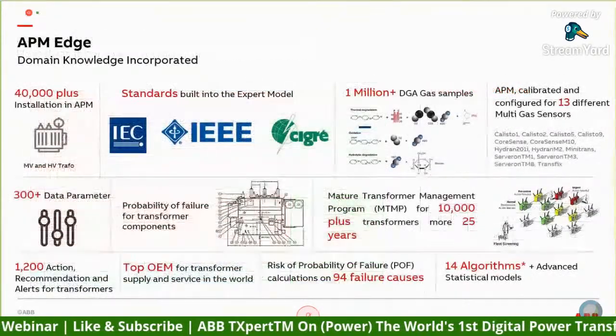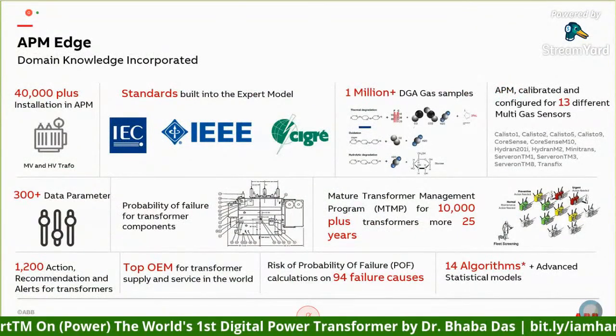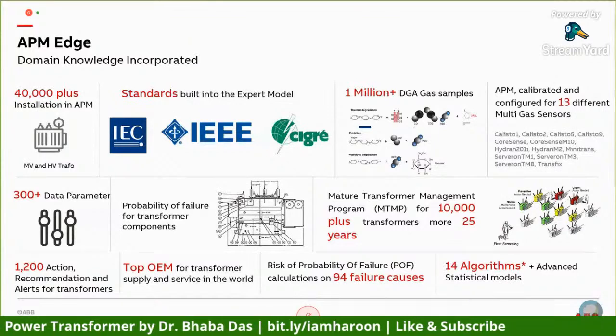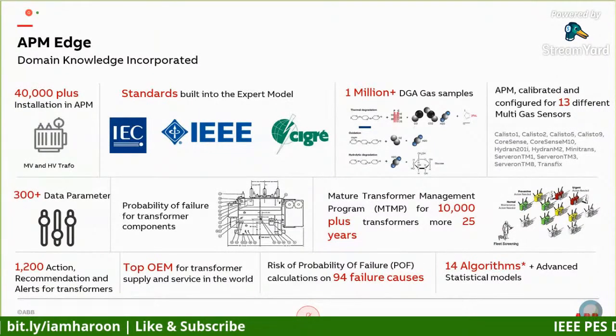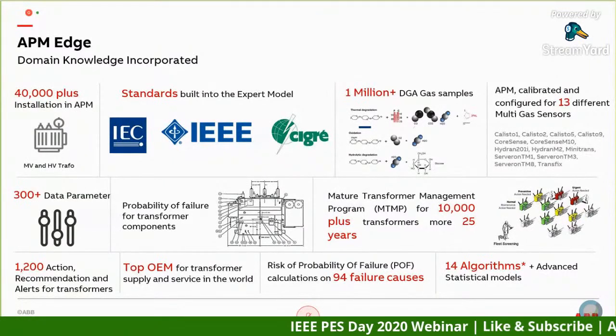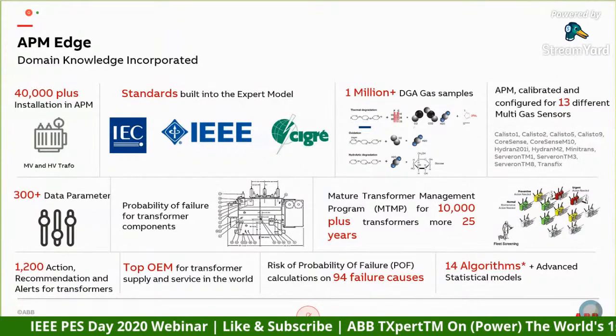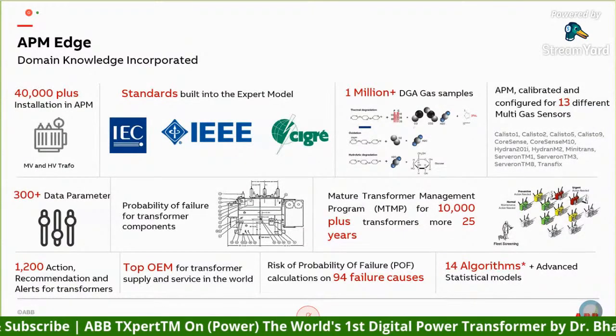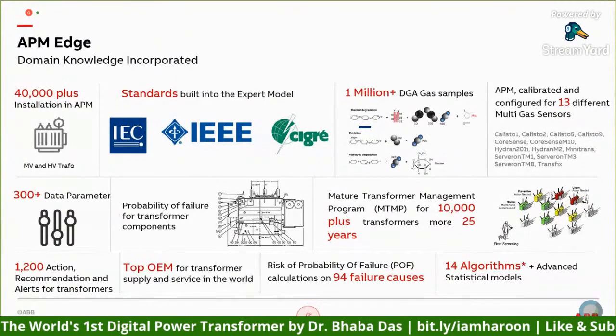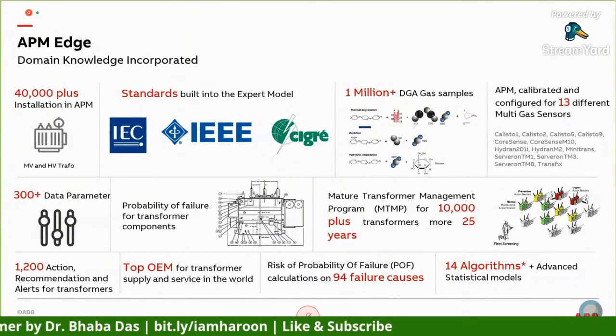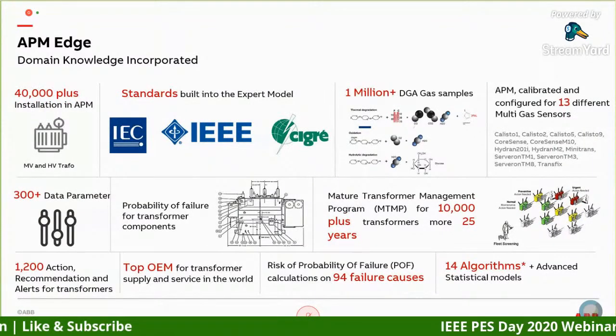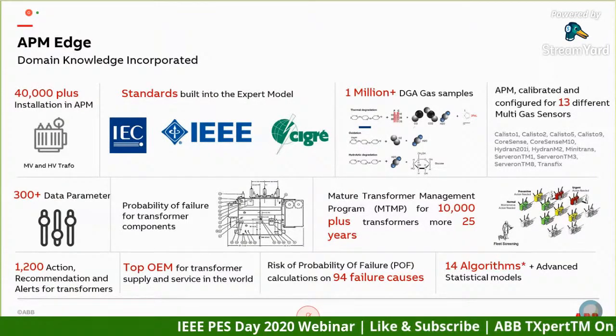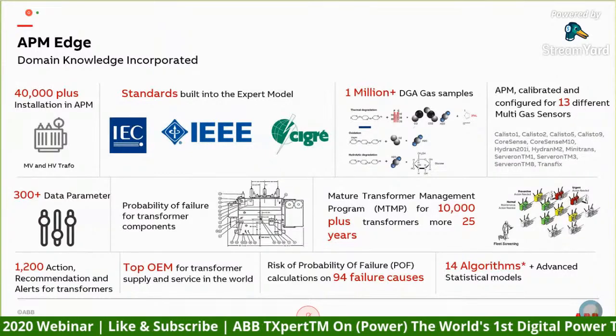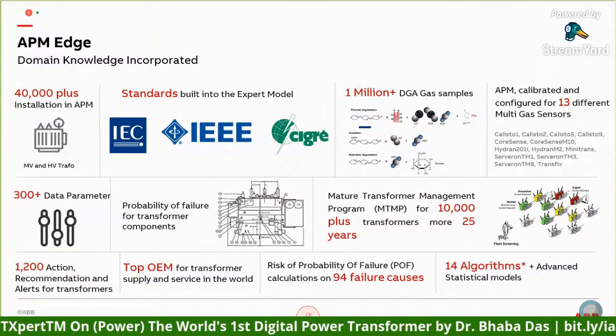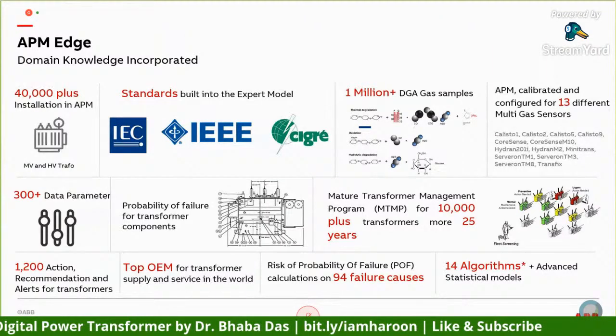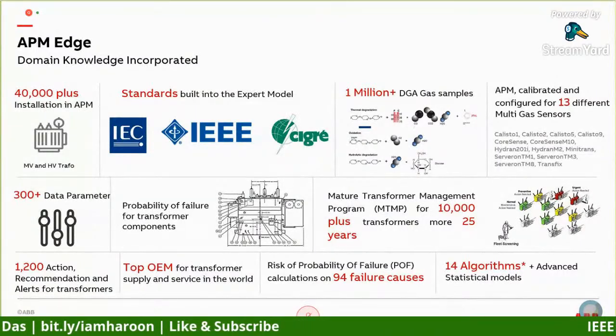So we have all the standards which are built into the expert model, whether it's IEEE, IEC, or CIGRE. We have lots and lots of DGA samples based on which we have developed all our algorithms. The software takes around 300 different data parameters. We calculate the probability of failure of each and every single transformer component and then aggregate it to give you a transformer failure probability based on all those subsystems. This is based on ABB's MTMP program, which we have run for many years. We have done condition assessment for more than 10,000 transformers only in North America, USA, and Canada.